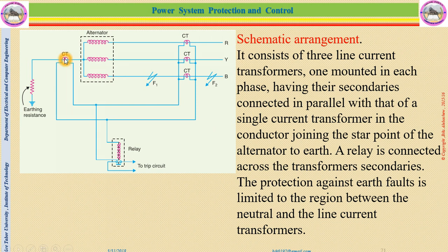As you can see here, this terminal is common for all. Ideally the sum of those three currents becomes zero, but practically it may differ a little bit from zero. So the sum of those three currents and the neutral current become equal at normal condition. This is the schematic arrangement of the balanced earth fault protection.